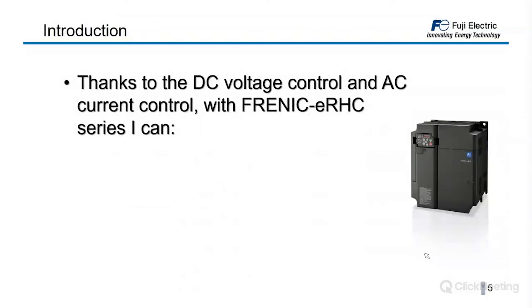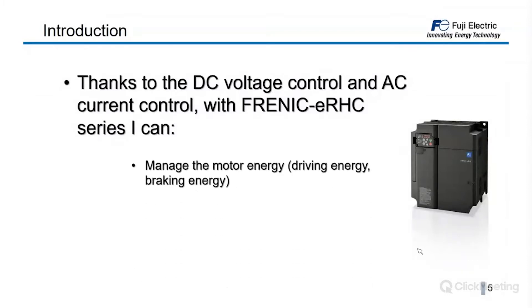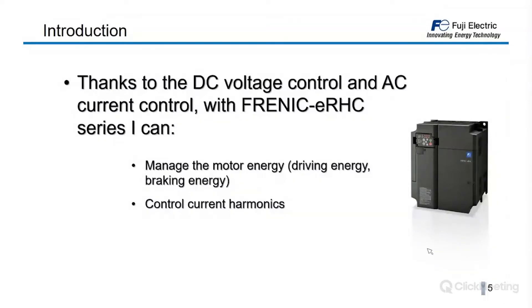This is where the FRENIC-eRHC series comes into play. Thanks to DC voltage control and AC current control, the FRENIC-eRHC can manage motor energy: when the motor is driving, the ERHe supplies the needed energy; when the motor is braking, the ERHe handles the energy and returns it to the mains. Thanks to the current control, it can generate an almost perfect sinusoidal wave on the input.